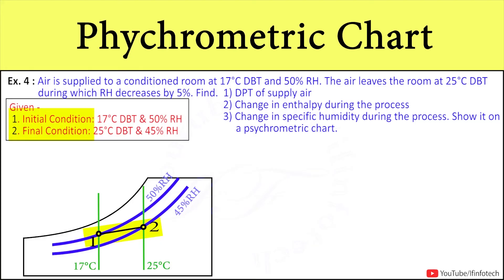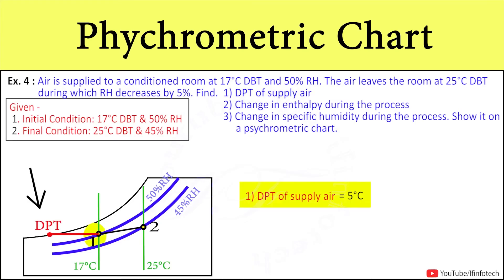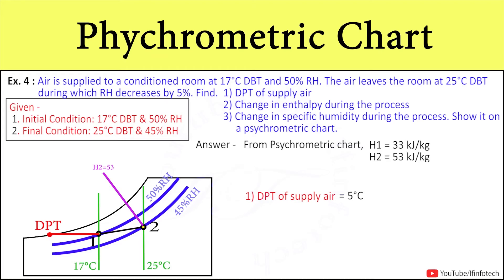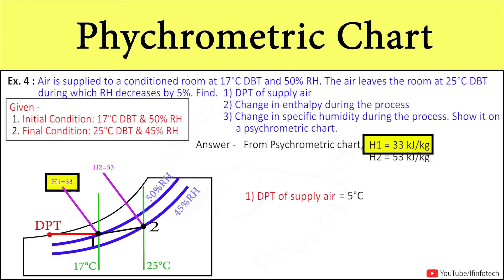We have the process 1 to 2. First, we want to find out the dew point temperature of the supply air. At point 1, the dew point temperature is 5°C. Next, we want to find out the change in enthalpy during the process. Enthalpy at point 2, which is H2, is 53 kJ/kg, and enthalpy at point 1, which is H1, is 33 kJ/kg.